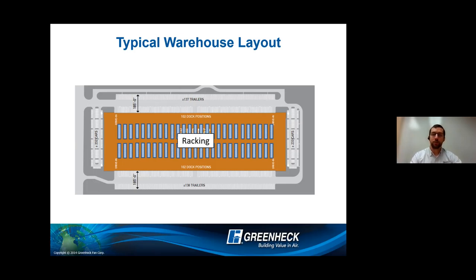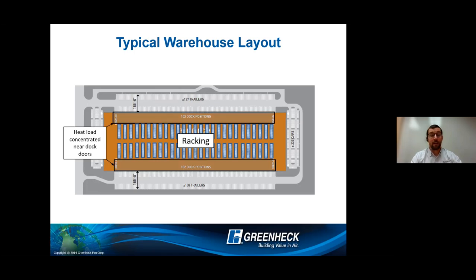So those are areas that are usually great places to position our equipment, because we have a nice open area to distribute the heat within the building. Additionally, when we think about our warehouse, that's where all our dock doors are. That's where a good chunk of our wall area is. So our heat load is really concentrated near these dock doors as well.